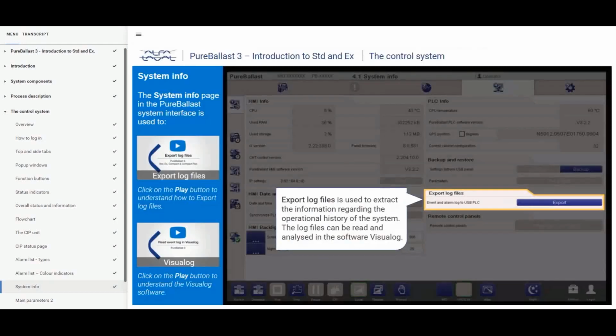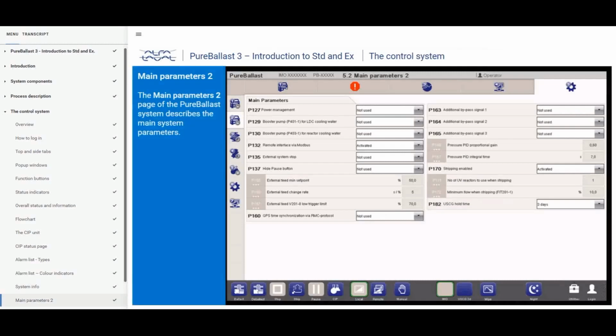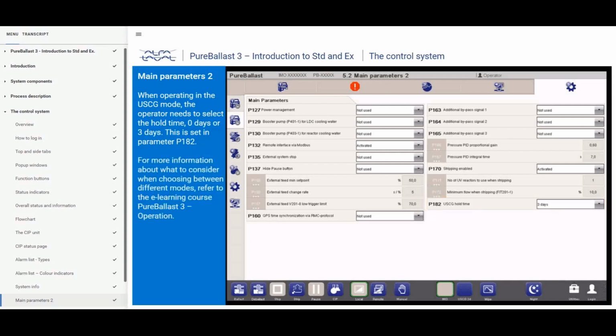Click Next to continue. The Main Parameters page of Pure Ballast 3 System describes the main system parameters. Most parameters on this page are set at commissioning and should only be changed by Alfa Laval's service engineers, except for P182. When operating in the US Coast Guard mode, the operator needs to select the hold time, 0 days or 3 days. This is set in parameter P182. For more information about what to consider when choosing between different modes, refer to the e-learning course Pure Ballast 3 Operation. Click Next to continue.